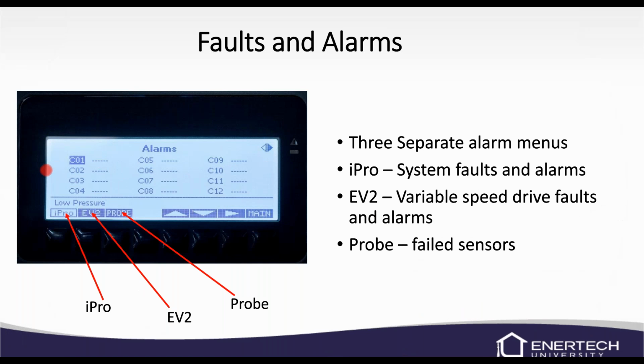Now we have 3 separate menus. You can see down here at the bottom, iPro. If it's white like this, that's the iPro alarms menu. If you need to go to the EV2, press the EV2 button. It'll take you to those faults and probe faults. The iPro, that's normally what you're going to see, like low pressure lockout, loss of flow, things like that. The EV2 is going to be a variable speed drive fault and alarm, and the probe is going to be failed sensors.